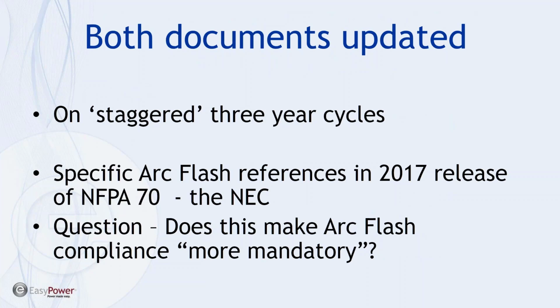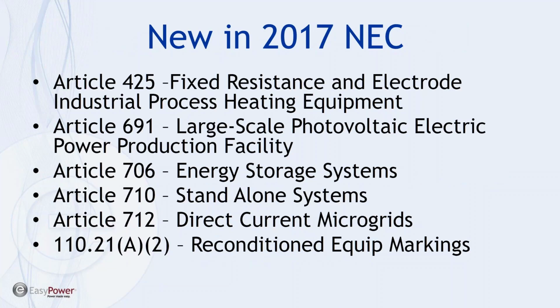Both documents are updated on a staggered three-year cycle. The 2017 version of NFPA 70 has some specific references to arc flash, and that's where I'm taking this discussion. The bottom line is, because there's now more specific information on arc flash in the National Electric Code, does that make arc flash compliance more mandatory?